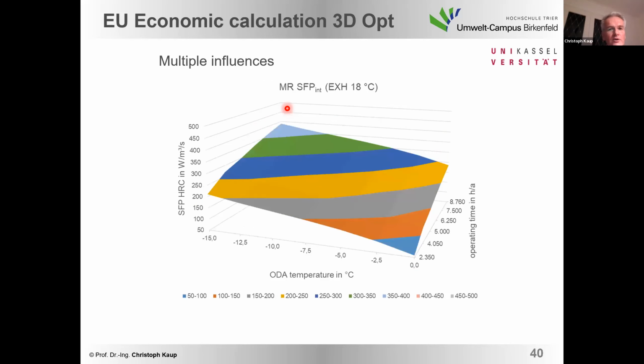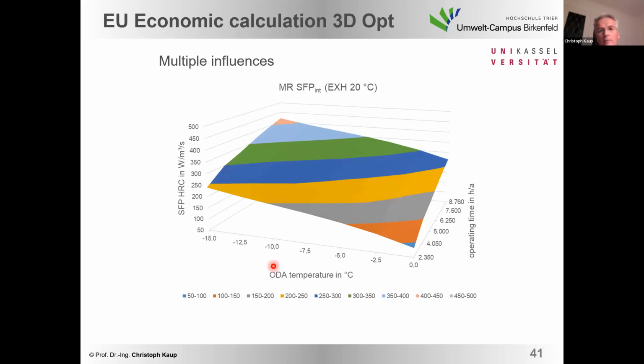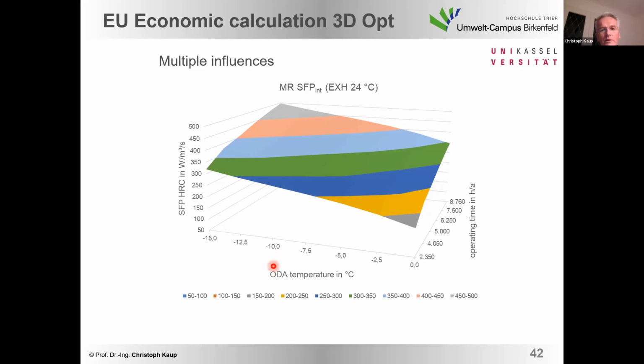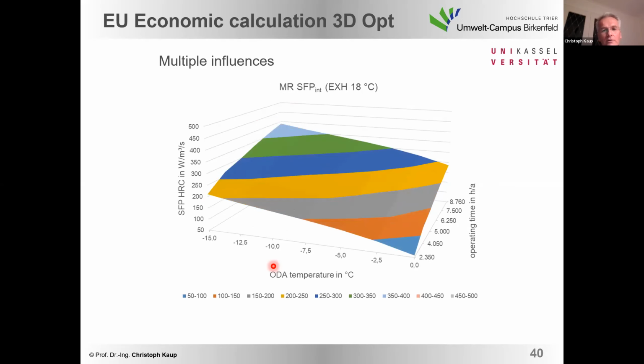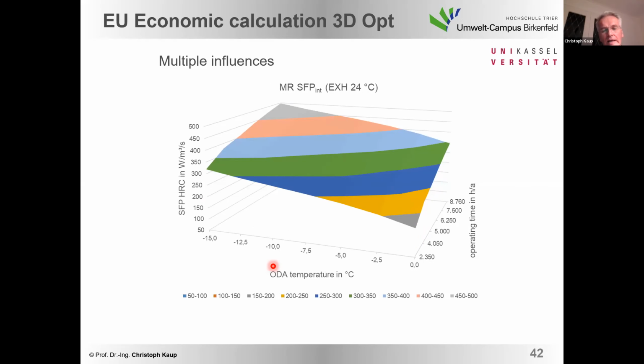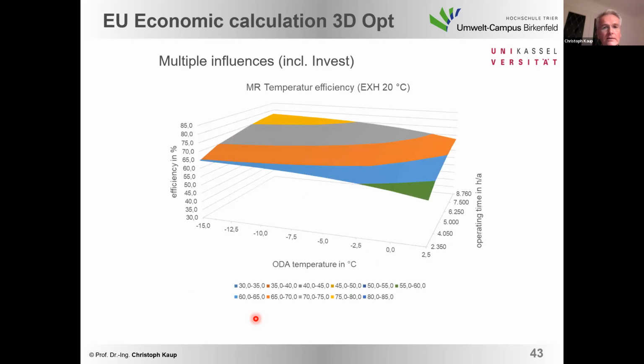And linked to the efficiency, we see also the shift of the SFP, the electric power consumption, also defined by the three influence factors. And at the end, you see if small heat recovery is required, we have small SFP factors, but if the heat recovery makes sense to be increased to maybe 80%, for sure, there's also a need for higher SFP values because the heat recovery will produce higher pressure losses than in the other cases.